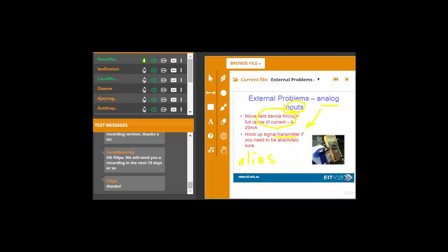So, remote troubleshooting, obviously just be aware. Today, we're all doing remote troubleshooting, but watch out for network security, because if you have your plant hacked, obviously major problems. Just a few other little points here. I just want to emphasize again, one of the things which is very unpredictable in any plant environment is obviously transients. Spikes, electronic, electrical spikes going through the system. We always think about lightning or something like that, but there could just be an Earth's potential rise due to an electrical fault. So, that could damage your input. So, the trick is there, try and use fiber optics where possible. And obviously, make sure you have good Earth grounding for your datacom systems between your racks. I've had a problem here with a common mode voltage problem, CMV, which caused me great angst.